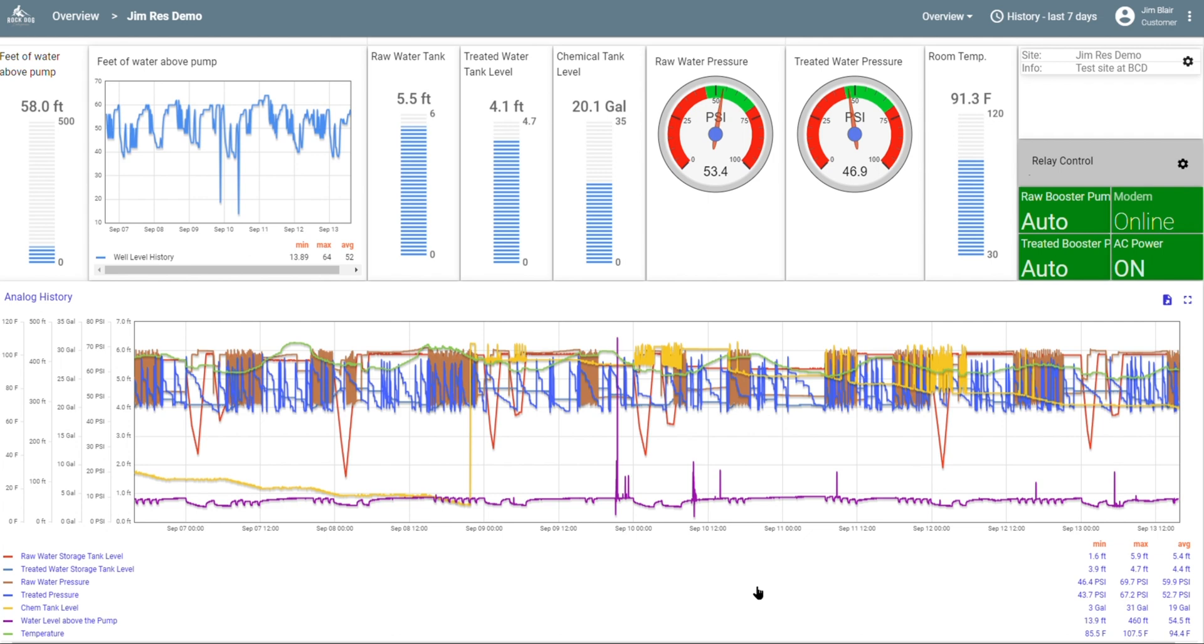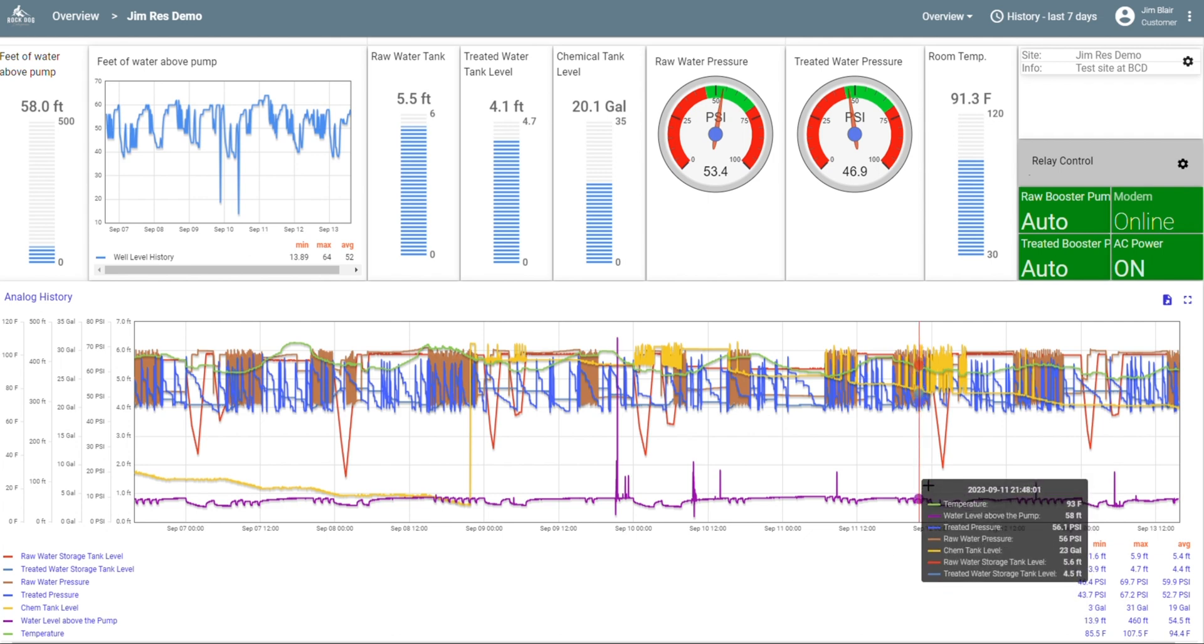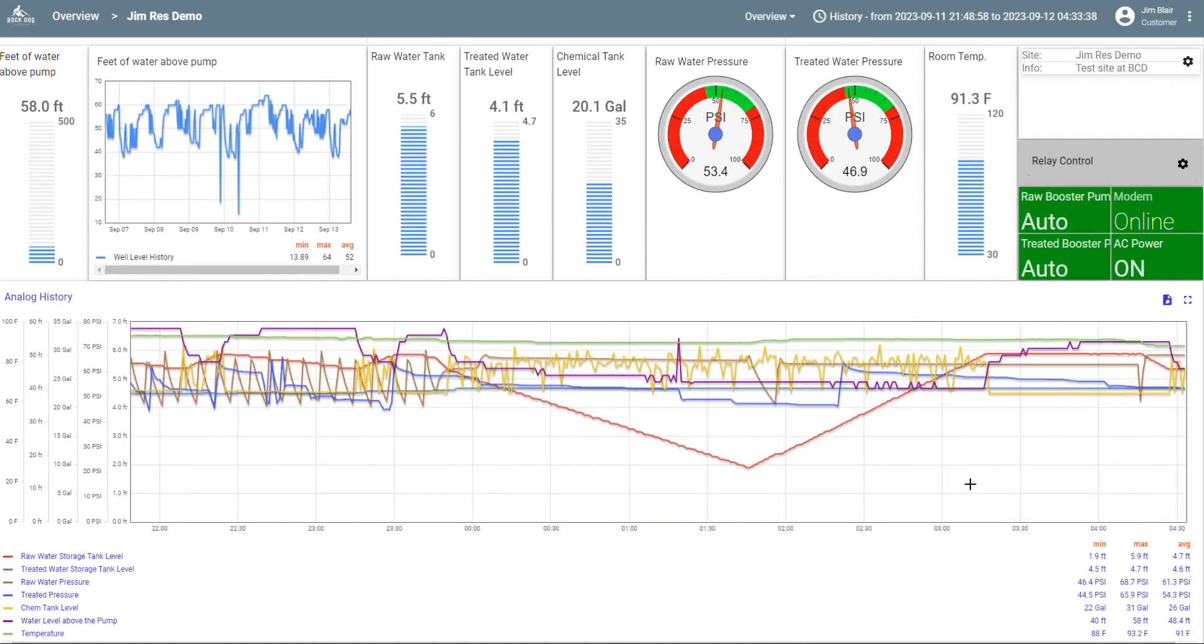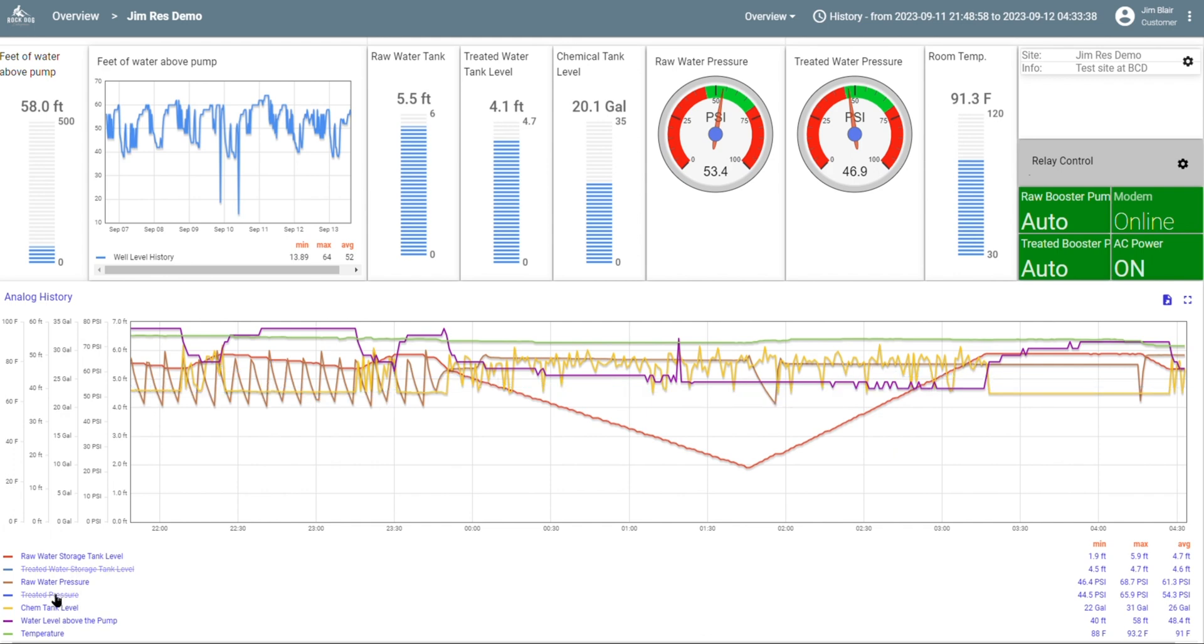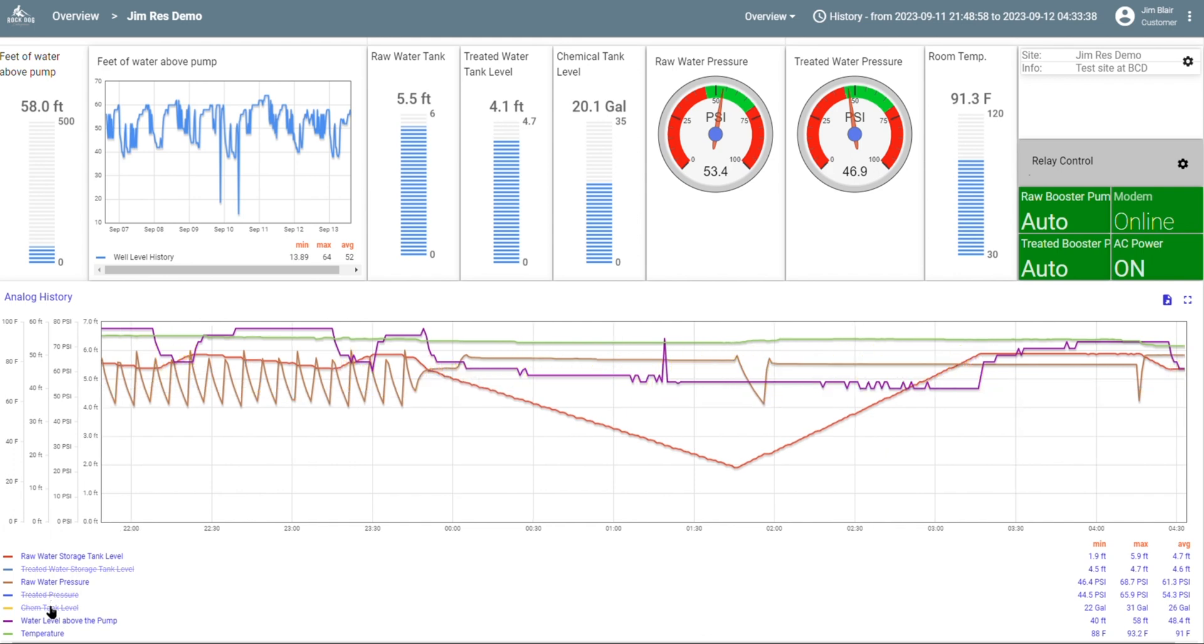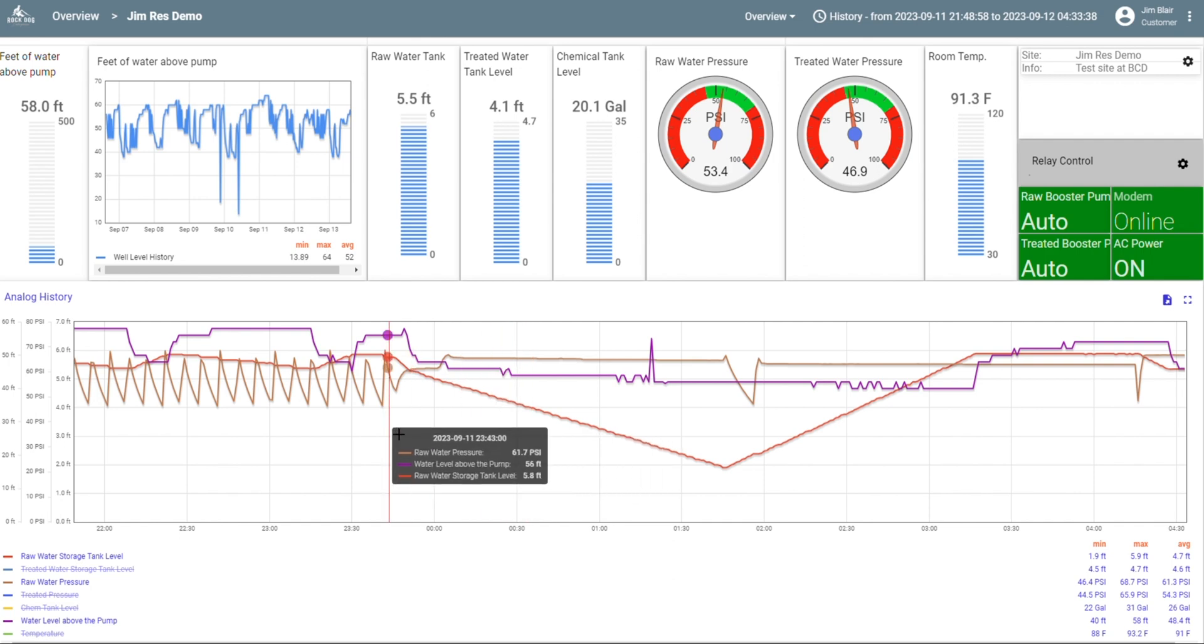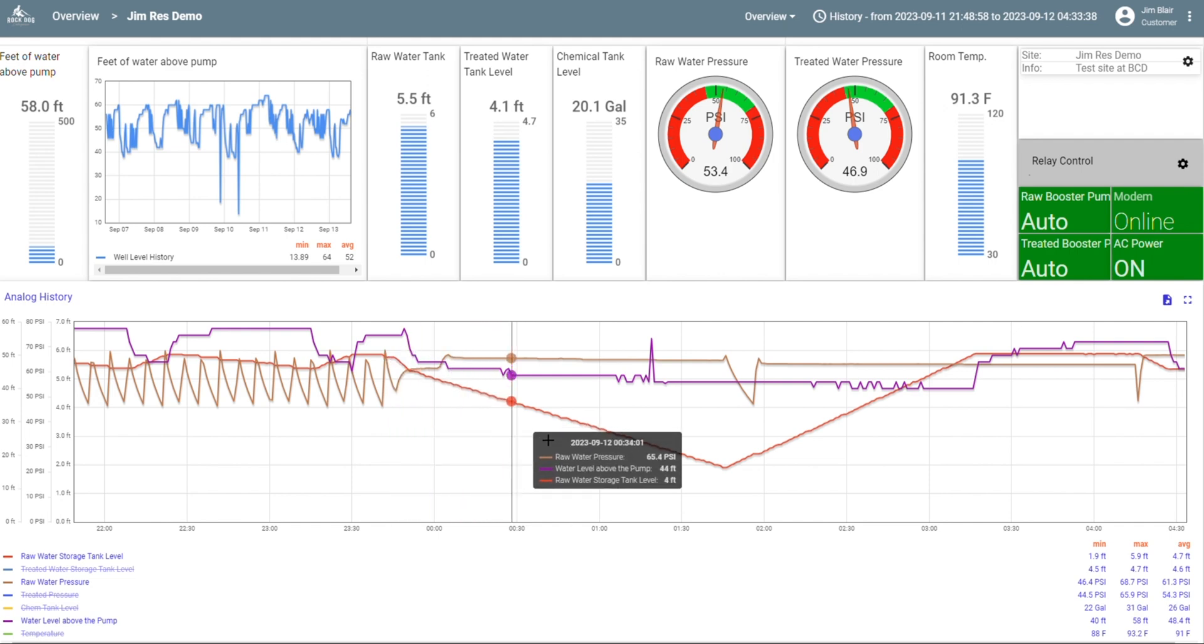For instance, my irrigation system ran the other night. How did my raw water system handle that demand? Well, let's turn off the treated water storage tank level, the treated pressure, the chemical tank level, and the temperature. We're left with just three things. The brown is the water pressure, the purple is the feet of water above my well pump, and the red is the water level in my storage tank. You can see my irrigation zone kicked on last night about 11:45 at night and that set of zones ran until about 1:45 in the morning.